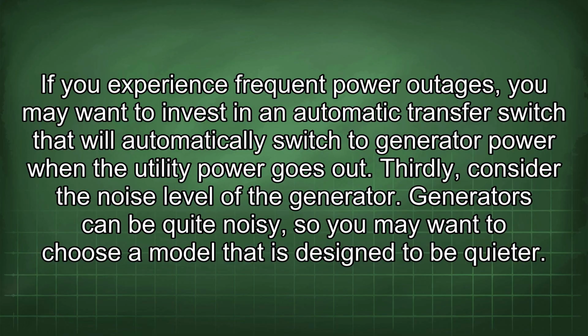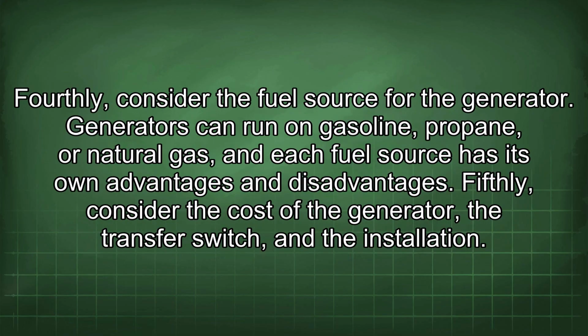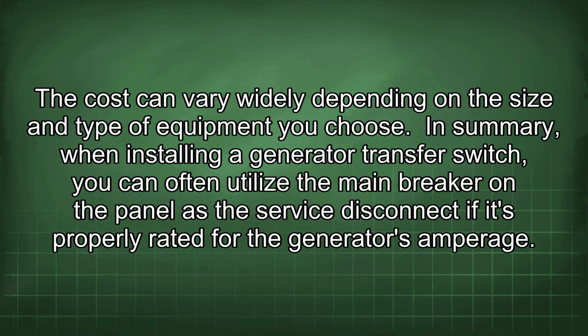Thirdly, consider the noise level of the generator. Generators can be quite noisy, so you may want to choose a model that is designed to be quieter. Fourthly, consider the fuel source for the generator. Generators can run on gasoline, propane, or natural gas, and each fuel source has its own advantages and disadvantages. Fifthly, consider the cost of the generator, the transfer switch, and the installation. The cost can vary widely depending on the size and type of equipment you choose.